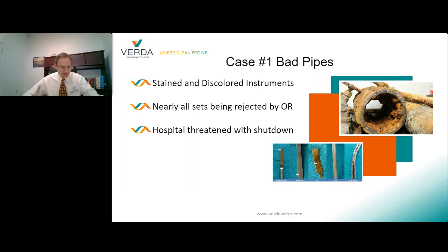In the short term, they leased a temporary mobile facility that purified the municipal water, removed the impurities causing the staining and spotting. Sterilizers with integrated steam generators were installed, eliminating the need to treat steam produced for the entire facility, right? So we're just doing steam for the department. And because these steam generators weren't designed to handle purified water, a food-grade polyphosphate was added to the steam feed water to raise the conductivity of the feed water to a level where the steam generators could function properly. And as soon as the temporary setup was operational, the staining issue went away. The long-term solution was to duplicate the successful short-term solution mobile setup inside the facility.